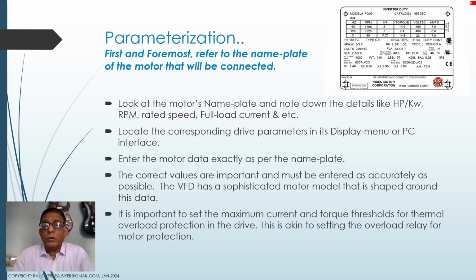Okay, do not accept the default values. The default values of rated current do not automatically follow the motor's kilowatt rating. Initially you'll get some value which is close, but for proper operation, you must go by the nameplate data.